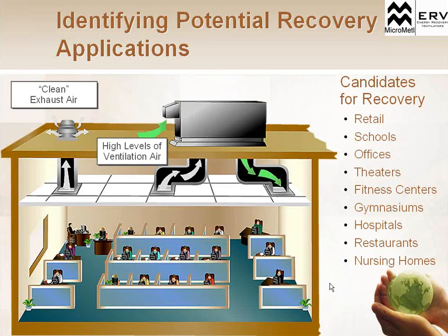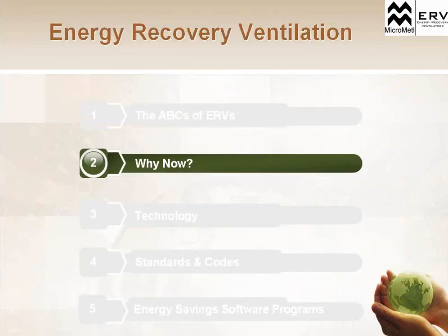So when we're looking at some of those applications, anywhere where we see high levels of ventilation requirements, retail stores, schools, offices are great applications. Theaters, where you have high ventilation loads for short periods of time. Fitness centers are obviously huge humidity generators, so we want to maintain that humidity level in that space. Gymnasiums, hospitals, restaurants, and nursing homes. These are places where we have a large amount of ventilation requirements and some humidity issues that we need to control. So we kind of understand what an energy recovery ventilator is.